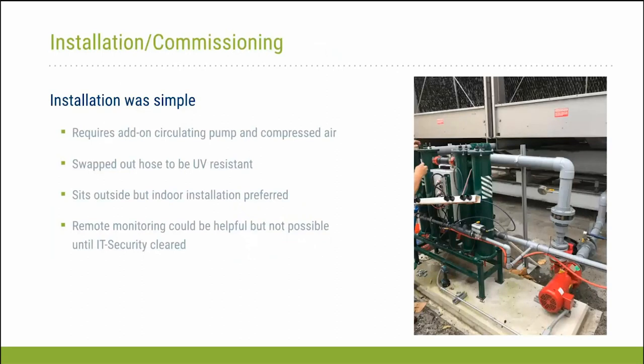So that's a picture of the unit again, and the installation was relatively simple and straightforward. You basically have 3 items you need to connect to the unit: water, side stream piping off of the cooling tower, power for the unit, which is very minimal, and then compressed air. The UET unit itself only requires 120 volt service at about 16 amps, so it's very minimal.